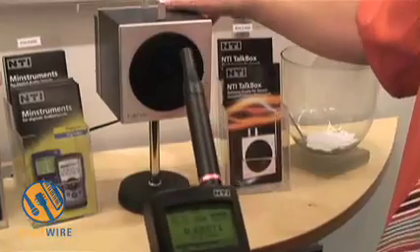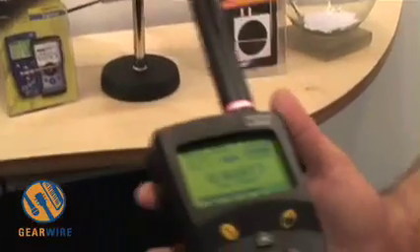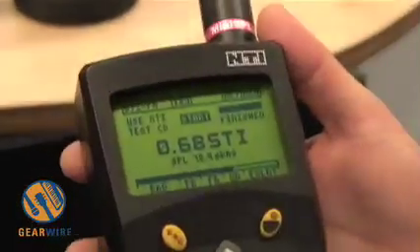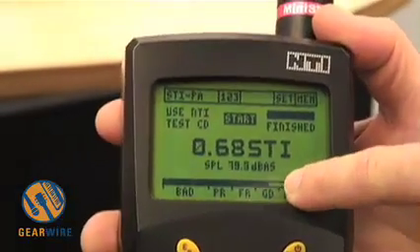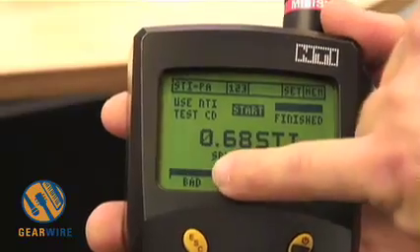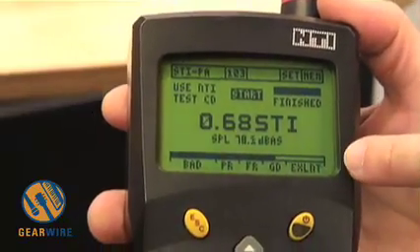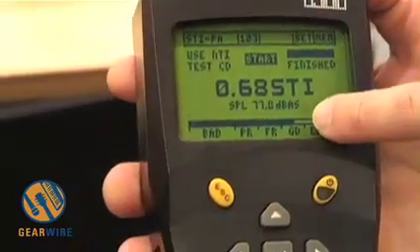I now mute the signal. What we see now, we have much ambient noise here, but we have good speech intelligibility. We have here a scale from bad to excellent. The measurement we took now is good.